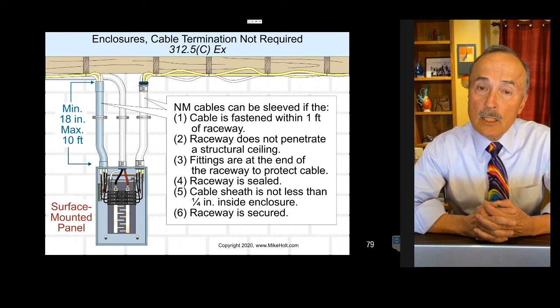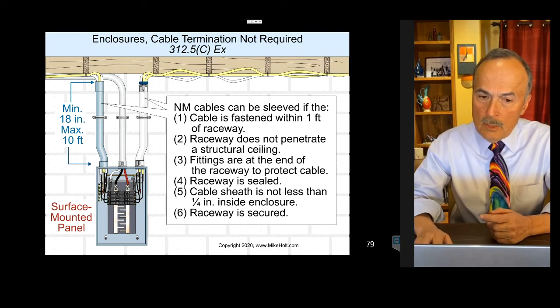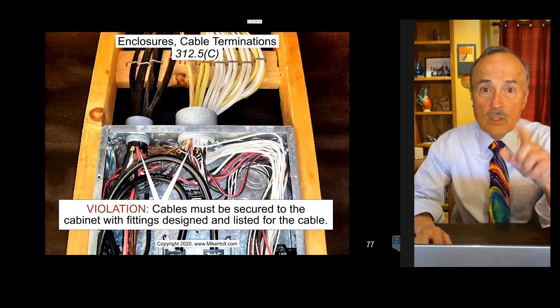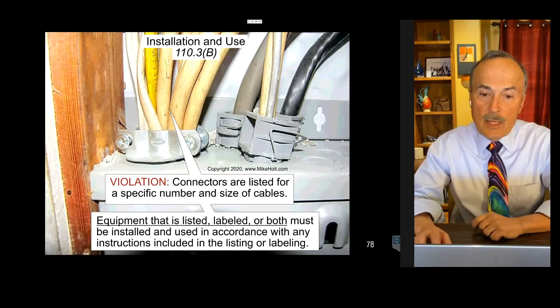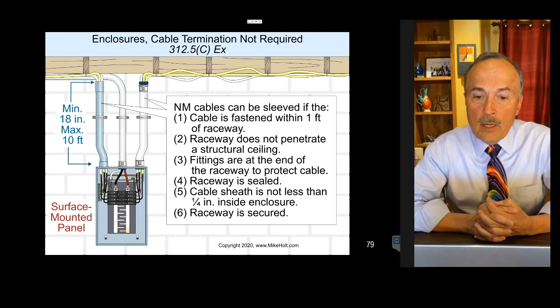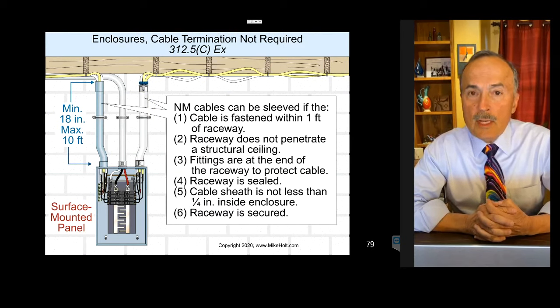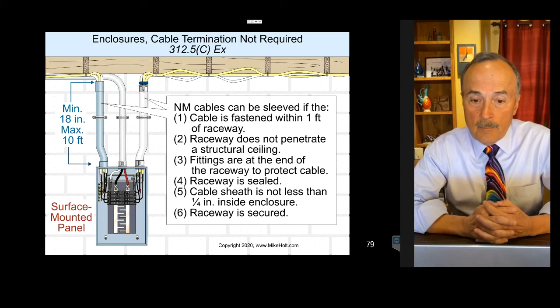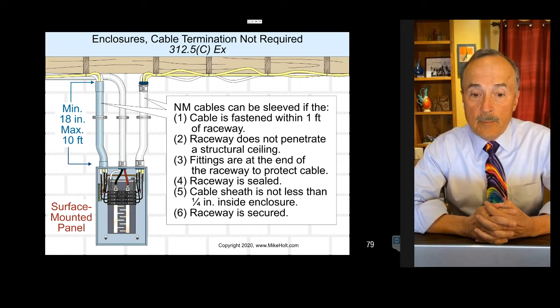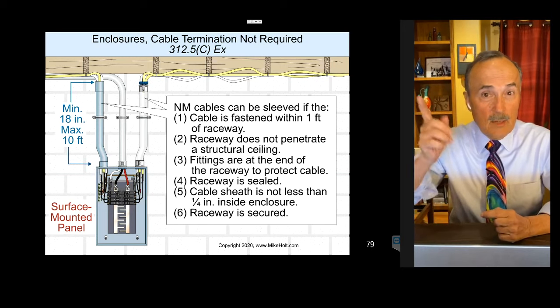Now, one of the guys on the stream last night sent me an email and said, but Mike, what about 312.5(C) and the exception? And I'm like, all right, let's review what this rule says. It says, hey, listen, if you want to run a bunch of NM cables, instead of doing that, put a little sleeve of pipe and get the sleeve going up, like I said yesterday, I really like. If you want to do that, here's what you've got to do. The cable is fastened within 1 foot of the raceway. Okay, no big deal. The raceway does not penetrate a structural ceiling.